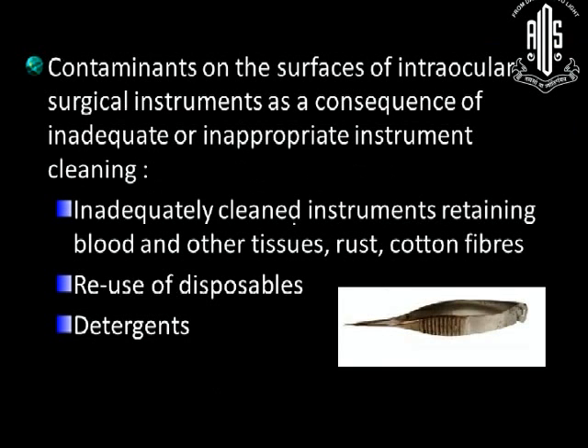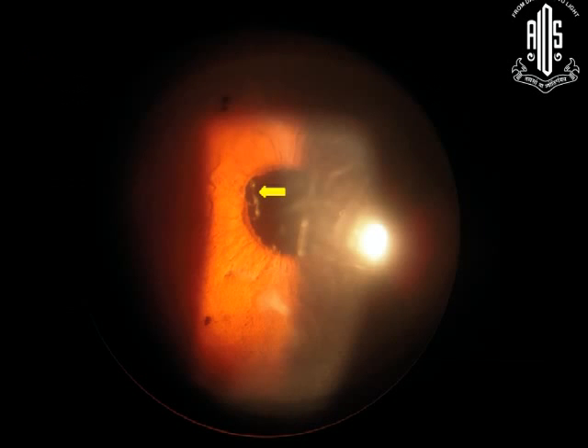Contaminants on the surfaces of intraocular surgical instruments as a consequence of inadequate or inappropriate instrument cleaning include: inadequately cleaned instruments retaining blood or other tissues, rust, cotton fibres, reuse of disposables, and detergents. Here is a case of mild TASS after uncomplicated phacoemulsification surgery — and look what we found: a cotton fibre in the pupillary area.